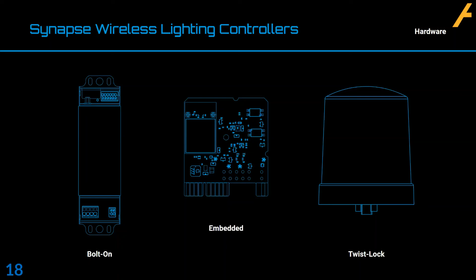The third way we control your fixtures, and you see these all the time, is a traditional twist lock. The traditional twist lock functions very similar to the bolt-on device. What's different with the twist lock is I have the ability to actually control 347 to 480 volt fixtures that are out there. I cannot do that with the bolt-on. With the embedded, it could be done if you were to install a Dali driver that is 480 volt.